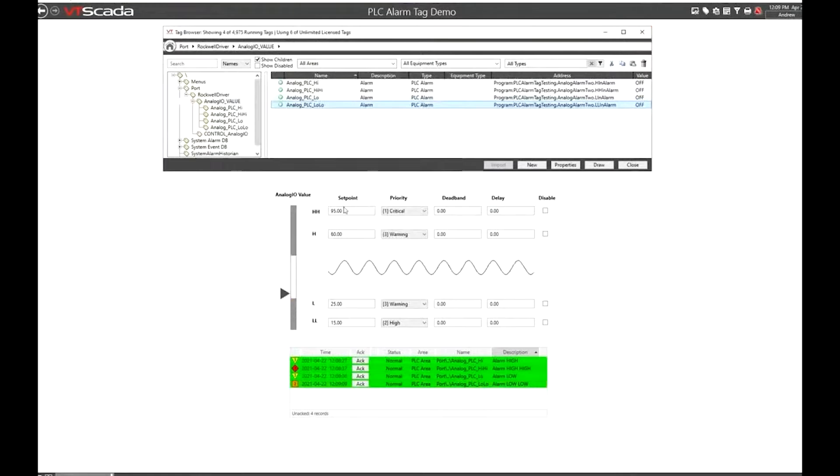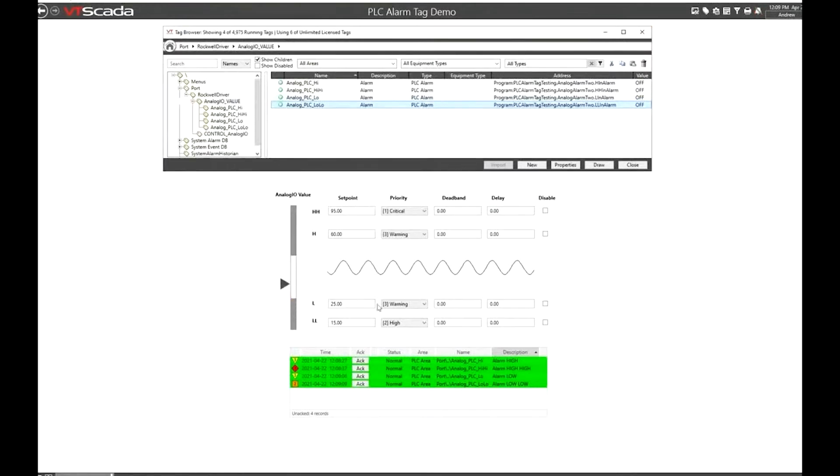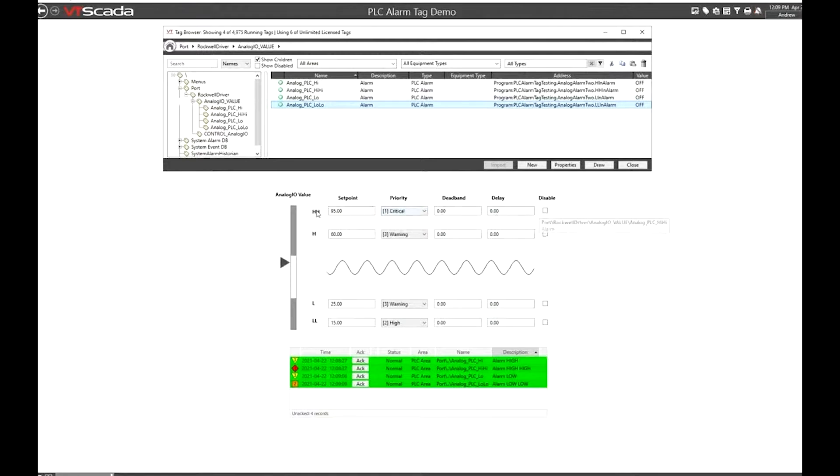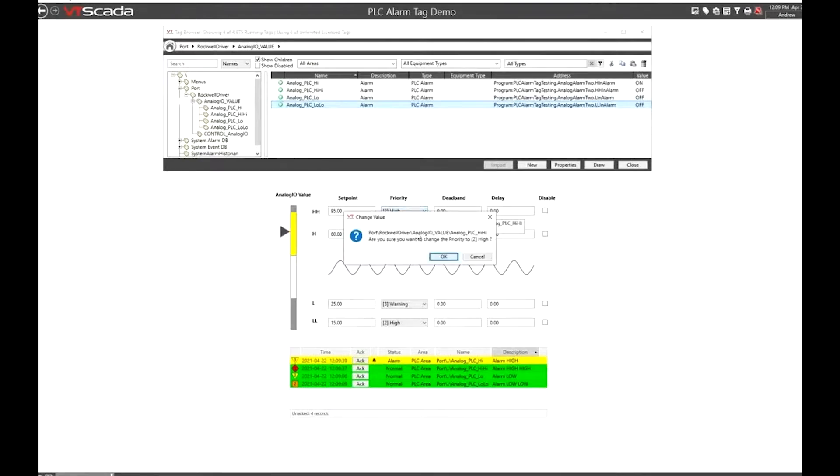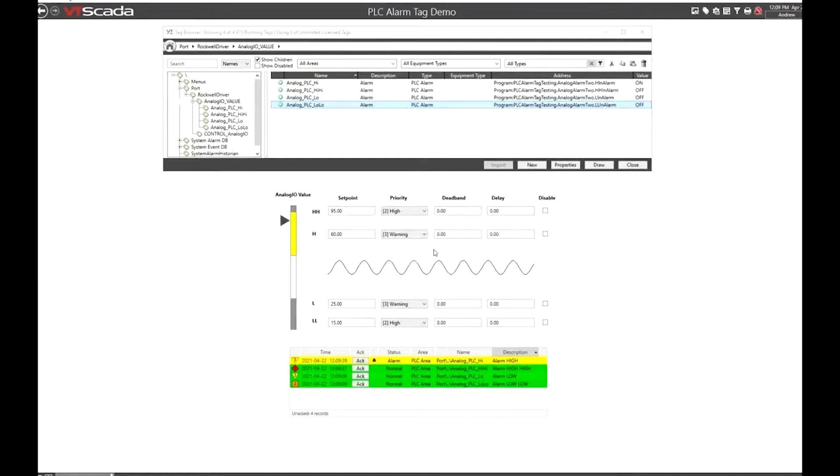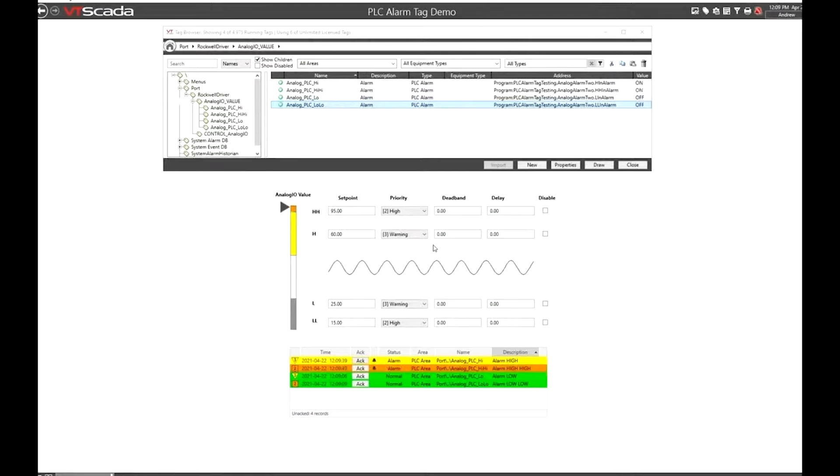I've drawn these four alarms on the screen here with the various configuration widgets. I can set for example the high high alarm set point priority, dead band or delay, and I can do that on the fly. But note that when I make these changes I may be controlling it from VT SCADA but all the information is being really set up in the PLC and the alarms are being determined in the PLC.